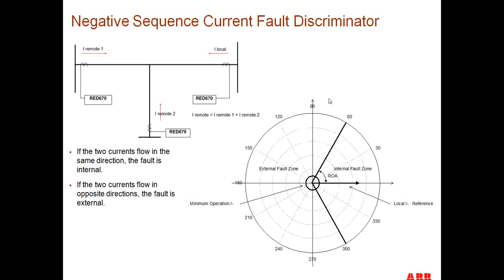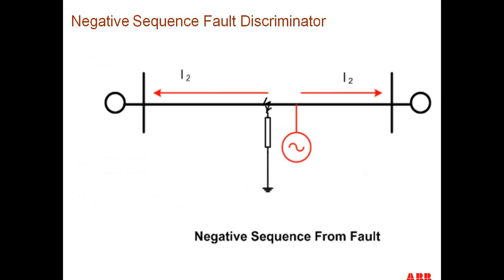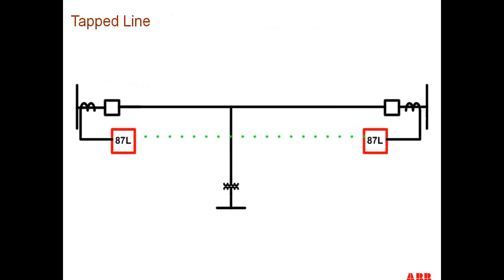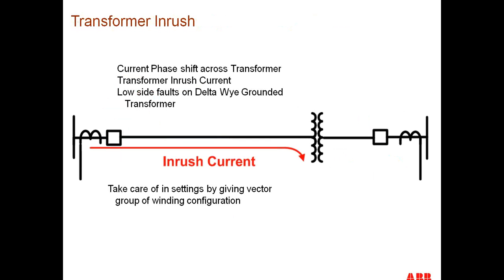Another question came in: can you please also discuss transformer inrush with auto transformer banks? I'm not sure what the question means. What we talked about before was regarding transformer inrush back here. I'm not sure what the question is. If you have a YY transformer here, then we don't have the problem of distinguishing this for our external fault problem. We don't need to use a zero sequence trap because the current will be going all the way through the Y-Y transformer. But as far as inrush is concerned, I'm not sure what the question is.